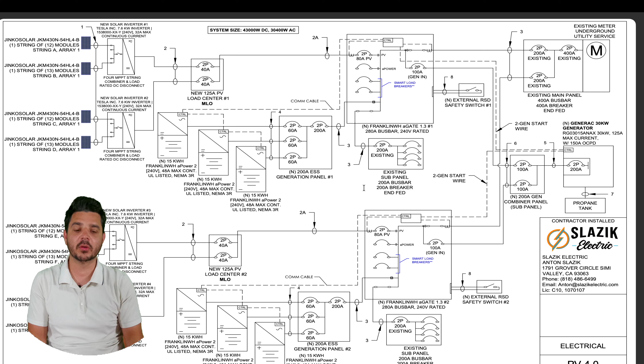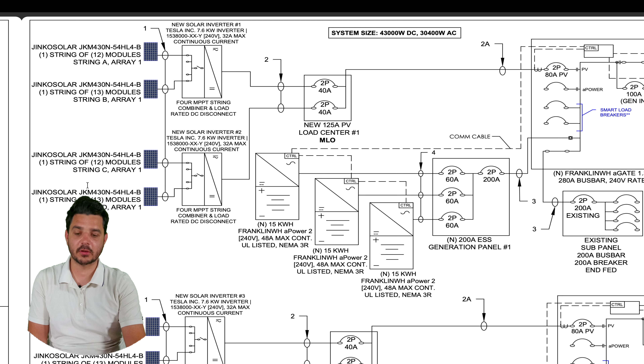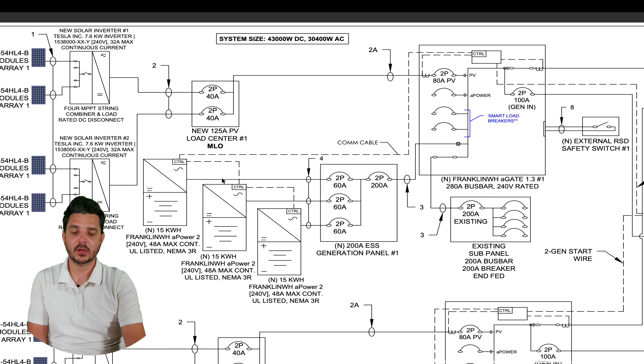It is a bit more complicated, and it is a little more expensive because you've got to buy twice as much equipment, right? You have to buy 2 automatic transfer switches, 2 emergency loads panels. You have to split the array in half. Usually you're buying equal amounts of batteries for both configurations. There's just different avenues on different things. So you can see we're doing a group of 12 and a group of 13 for the inputs on the Tesla Solar Inverters, and then, like I said, that goes to a load center that's combining the 2 solar inverters. So here we go again, a string of 12, a string of 13, very straightforward, nothing out of the ordinary here.